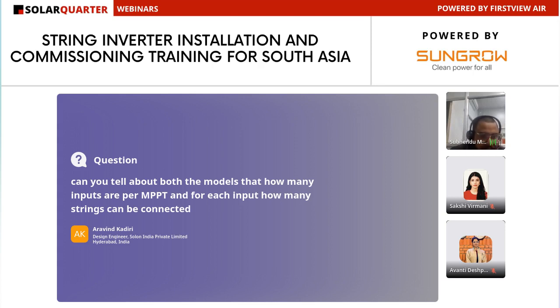Can you please tell about both the models, how many inputs per MPPT and for each input how many strings can be connected? In a single MPPT, two inputs are there, and the strings depend on the string current.